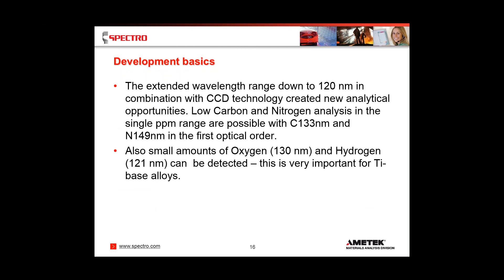The extended wavelength range down to 120 nanometers, in combination with CCD technology, created new analytical opportunities. One was low carbon and nitrogen analysis in the single parts-per-million range — the carbon-133 nanometer line and the nitrogen-149 nanometer line in the first optical order. Other benefits discovered searching in that wavelength range include an oxygen line at 130 nanometers, and way down at 121 nanometers we could detect hydrogen — very important in titanium-based alloys.